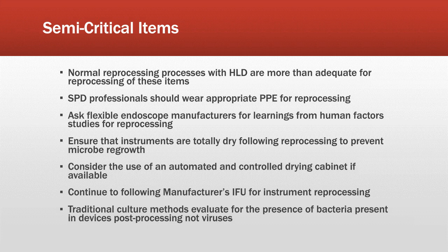And so it's not only a good idea to make sure that the instrument is dry, but if you have the capability of using something like a drying cabinet, especially one where the temperature and humidity is controlled and there's a forced air dry, that's going to be even more powerful to making sure that these instruments are not recontaminated after the reprocessing process. And lastly, one thing that's come up a lot is, should we culture for coronavirus? And there is no recommendation at all to do that. And viral cultures can be pretty problematic to collect and grow.